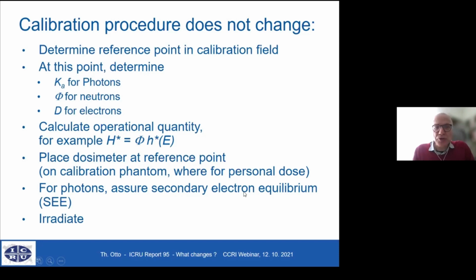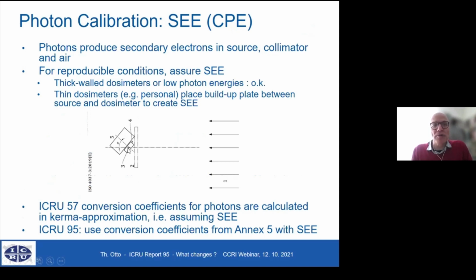And then for photons, in addition, you have to assure secondary electron equilibrium to have reproducible conditions. This whole obligation to calibrate photons in secondary electron equilibrium comes from the need that in a calibration facility, you need to be reproducible from Braunschweig over Paris to Denver and God knows what else calibration facilities are there at different places, at different height over sea level and so on, and in different calibration labs where the secondary electron spectrum of the pure calibration source could be very different. But by placing the so-called build-up plate in front of the dosimeter, which is either mounted on the phantom or for certain types not, you create artificially secondary electron equilibrium, and you can compare the calibration coefficients obtained in any calibration laboratory in the world.